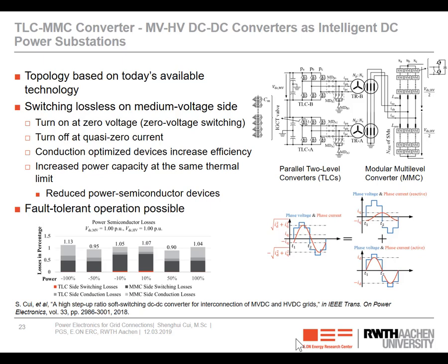One problem of the dual active bridge today is that it presents very high efficiency in full load situations, but quite poor efficiency in partial load situations. If you go back to the previous slides, in accordance with our calculations for the 7.5 megawatt DC-DC converter at our institute, at full power the efficiency is as high as 99.2%, but in partial load conditions, especially, let's say, 10% of the rated power, the efficiency drastically decreases to only 96%.